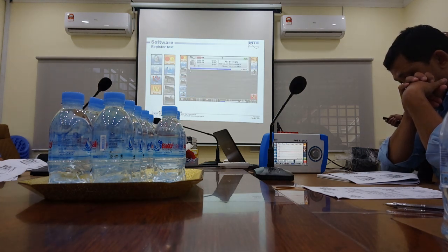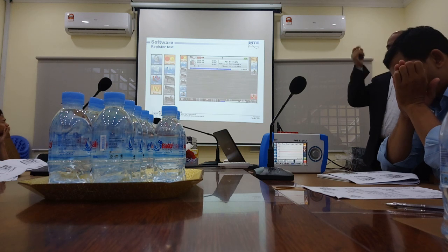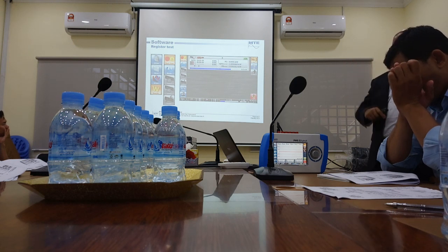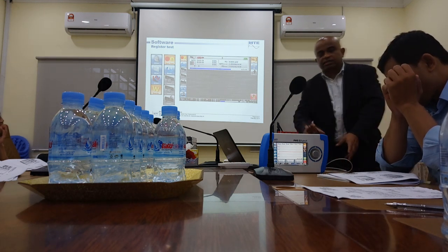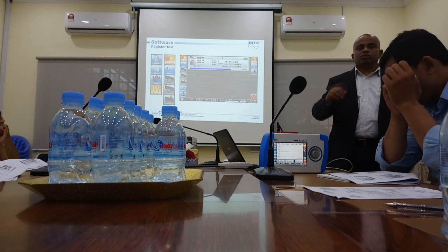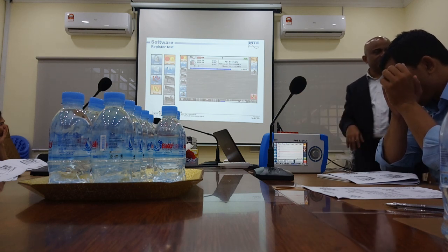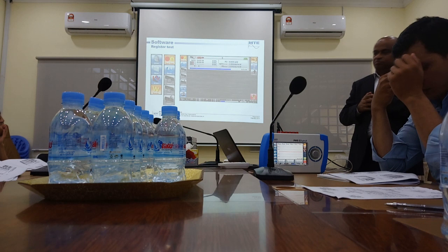Okay, this is another area where you manually enter. For example, you have no pulse, maybe the LED is not working, or the rotating disc is too dirty, you cannot measure anything. Okay, then you enter the value, starting value, ending value. Okay, it means like that. For example, you connect this standard also to the site. Okay, so you switch off the loads as much as possible, and you note what is the reading. Then you maybe go back, wait for some 30 minutes or 1 hour, come back, put the new value in, then it will tell you what is the error. Okay?